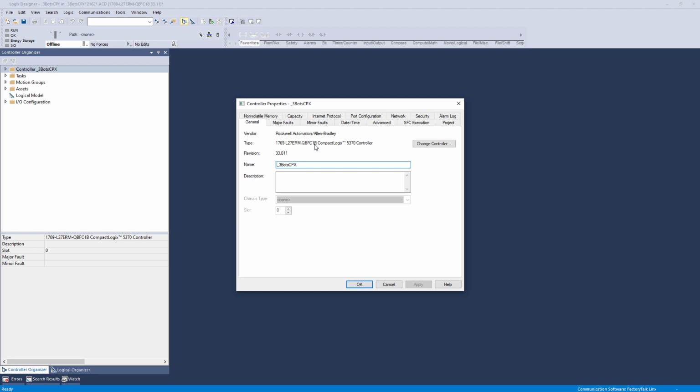A controller has I/O, a processor does not. A processor plugs into a chassis or connects into a system of backplane that then picks up I/O modules on that backplane. Whereas a controller, this particular one, has all of that built into the plastic box.